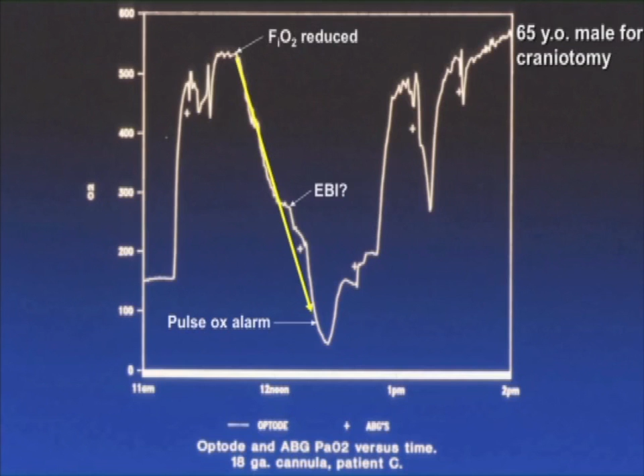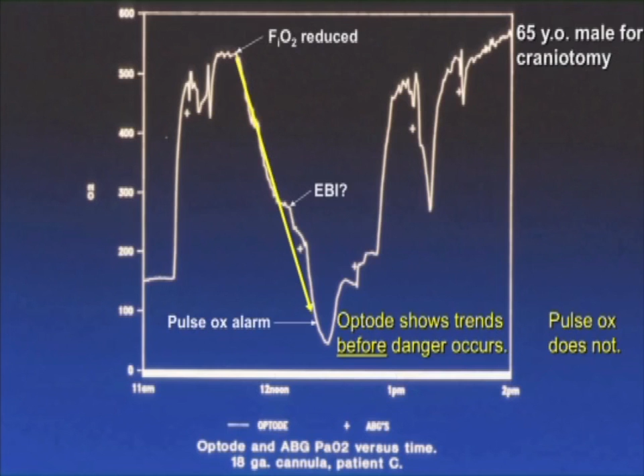And that is one of those physiologic limitations. We'll talk about that one more time. The Optode shows trends. This is not dangerous up here. This is not even dangerous down here where it's dropping below 200. But it's telling you, hey, something's wrong. Something's happening here that is not what we expected. You better look at the patient and see what's going on. The Optode gives you an early warning. The pulse oximeter does not, of these kind of changes.